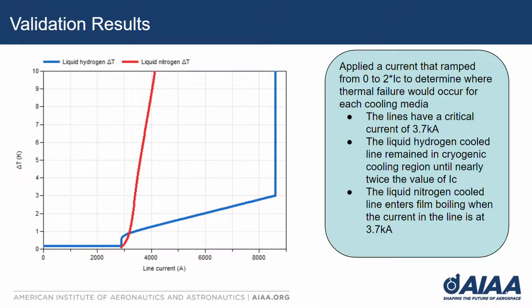Here we have the results where we apply the current from 0 to twice the value of IC. This helps us determine where thermal failure would occur for each cooling media. Both lines have the same critical current of 3700 amps. Liquid hydrogen, shown in blue, cools the line until nearly twice the value of IC. The temperature difference between the line and the cooling media slowly increases before sharply increasing at about 8500 amps. Whereas for liquid nitrogen, this occurs when the line hits the critical current at 3700. This shows that liquid hydrogen does have some buffer included in the media itself, so we can size the line and include protection accordingly, and use the media as a form of protection as well.